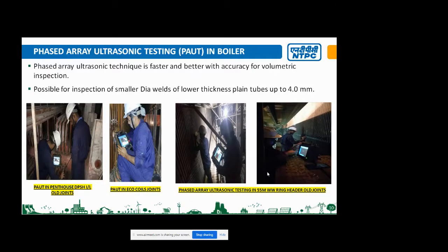We are normally inspecting 4,000 to 6,000 joints in every overhaul, and we inspect all the old joints in the penthouse area, eco coil joints, and even our intermediate header joints using this system. We are able to eliminate many welding defects which may cause a later forced outage. So this system helps a lot in reduction of our forced outage due to BTL.